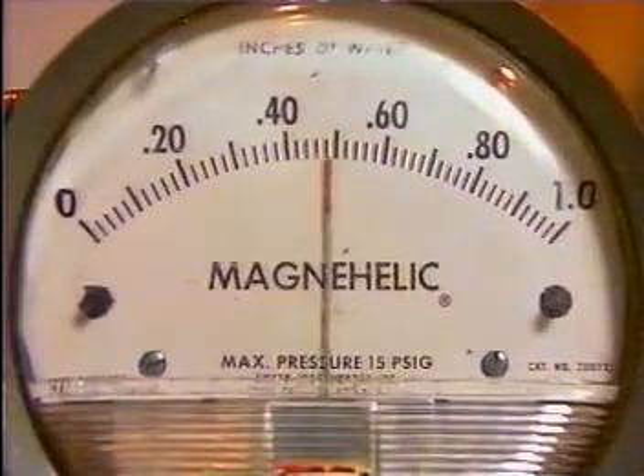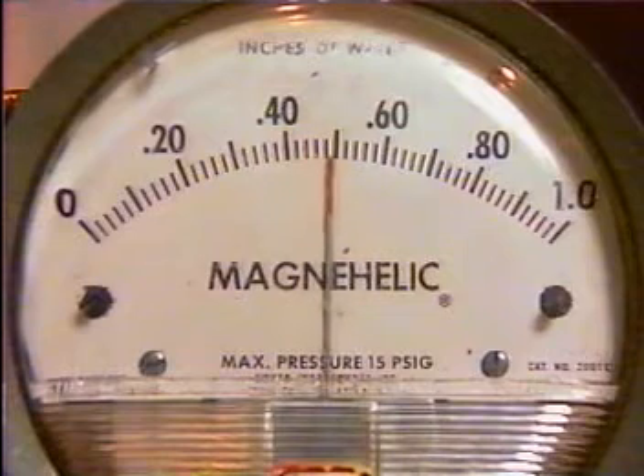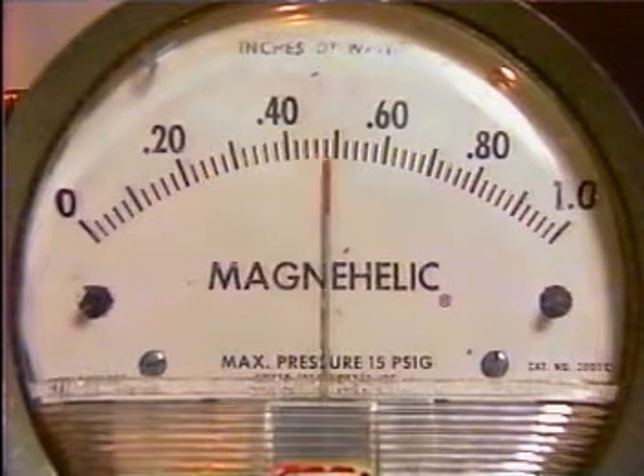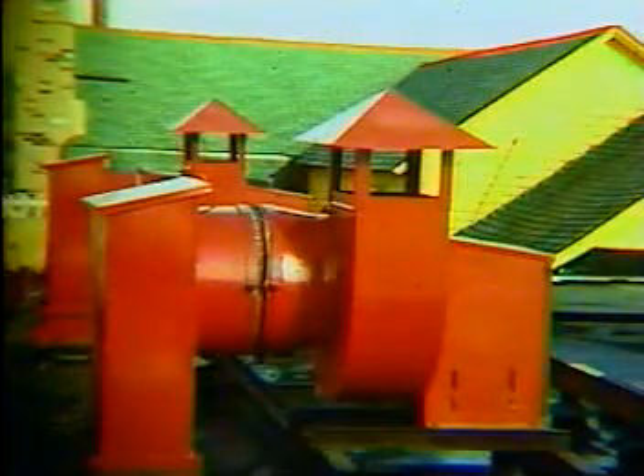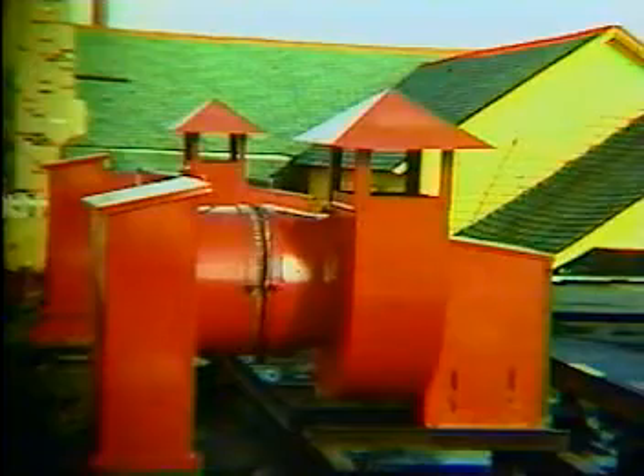The Magnehelic gauge shows a performance drop of roughly 1/2 inch static pressure, from 1 inch all the way down to 5/10 of an inch. In this example, the weight and the velocity of the air work against the fan by forcing air past the fan inlet. The turbulent air flows back to the fan inlet. Such poorly designed inlet ductwork is unfortunately all too common.